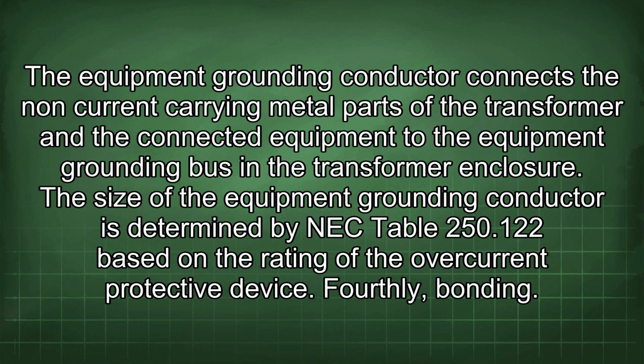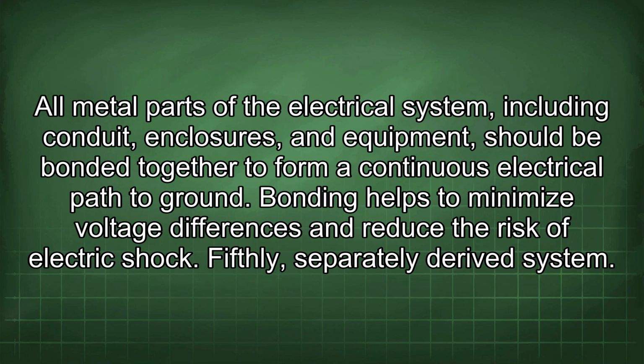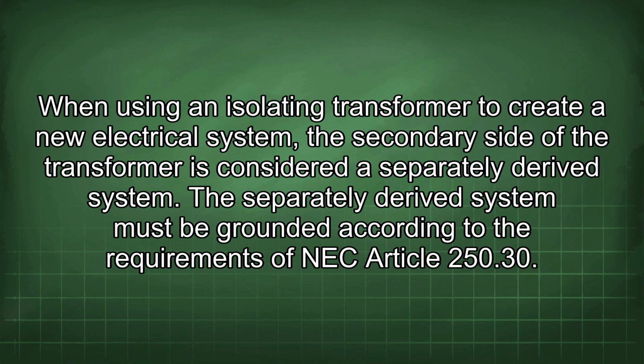Fourthly, bonding. All metal parts of the electrical system, including conduit, enclosures, and equipment, should be bonded together to form a continuous electrical path to ground. Bonding helps to minimize voltage differences and reduce the risk of electric shock. Fifthly, separately derived system. When using an isolating transformer to create a new electrical system, the secondary side of the transformer is considered a separately derived system.